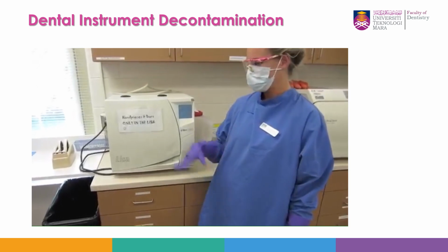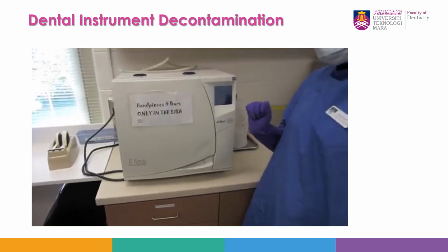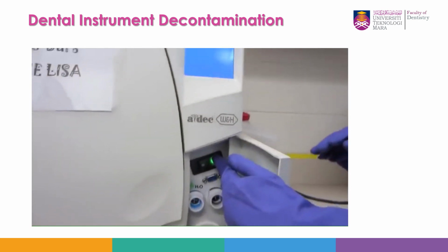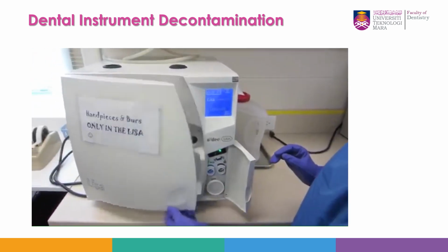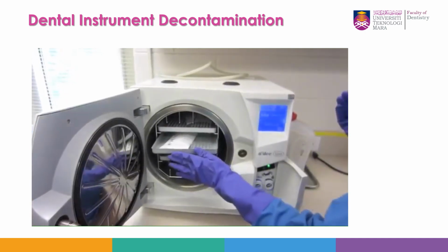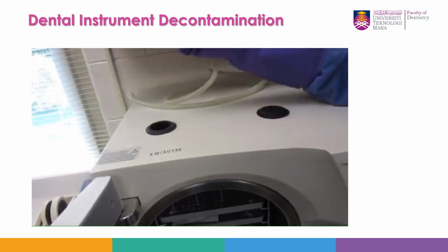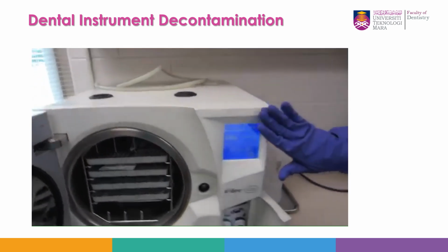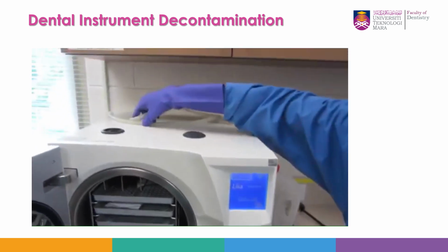For handpieces and burrs, you would use the Lisa. Turn on the Lisa. Load packs and bags loosely into shelves inside the chamber. Fill the water reservoir until a beep sound indicates full. If directed by the screen, empty wastewater contents with the drainage hose. Plug into the gray connector.